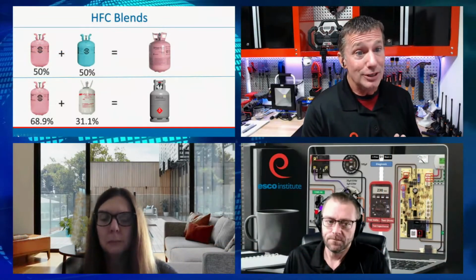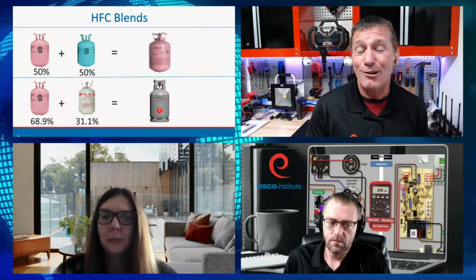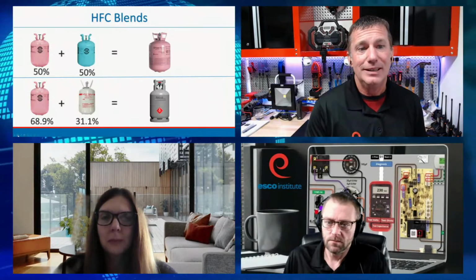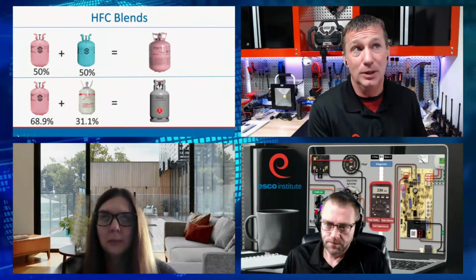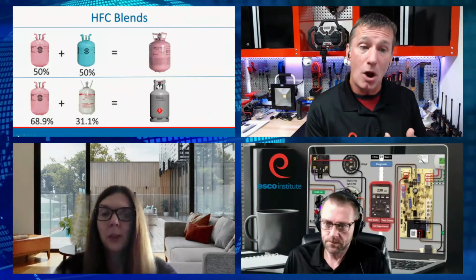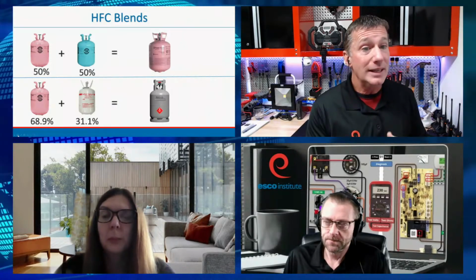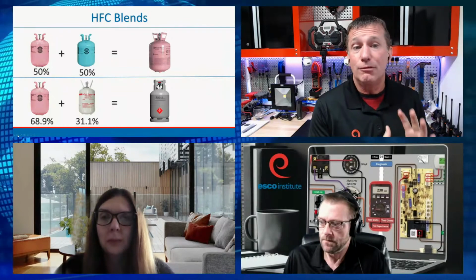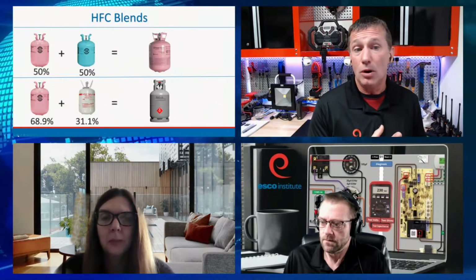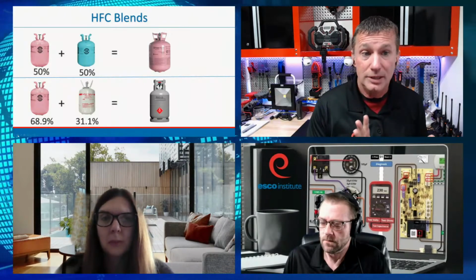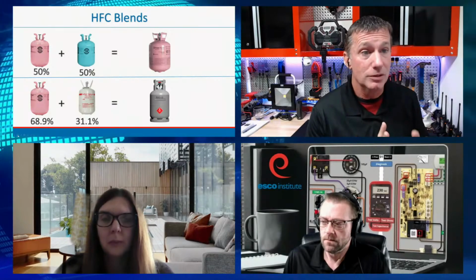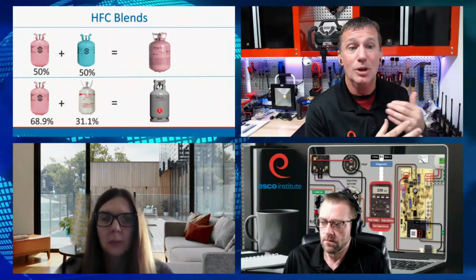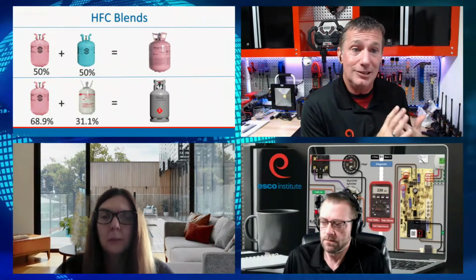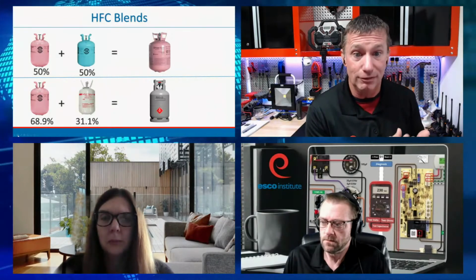So R32 is actually half of that R410A you've been working with. R410A is a 50-50 blend of R32 and R125. We're going to continue to use R32 in a variety of applications, and we'll see R32 on its own, which makes it a slightly flammable refrigerant.